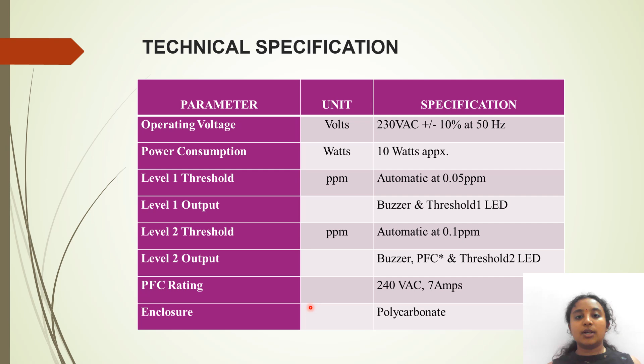Technical specification. Operating voltage should be around 230 volts AC, and it may be plus or minus 10%, at 50 hertz, and power consumption is approximately 10 watts. Level 1 threshold is 0.05 parts per million. Level 1 output is the buzzer and threshold 1 LED. Level 2 threshold is 0.1 ppm or parts per million. Level 2 output is the buzzer and threshold 2 LED, and it also activates the relay. The rating is 240 volts AC, alternating current, 7 amps. Enclosure is polycarbonate.